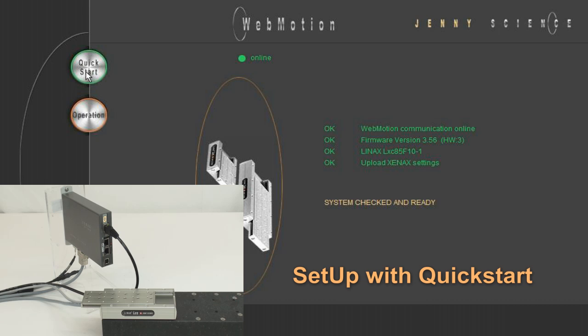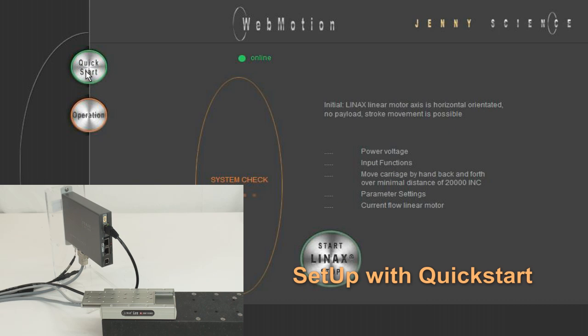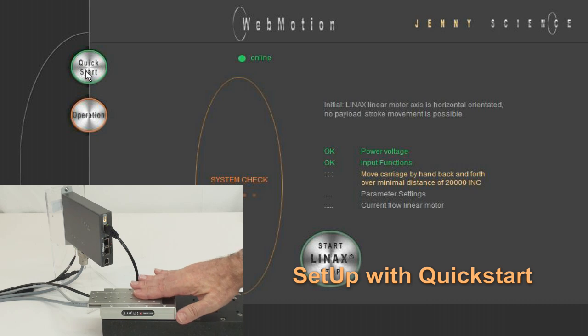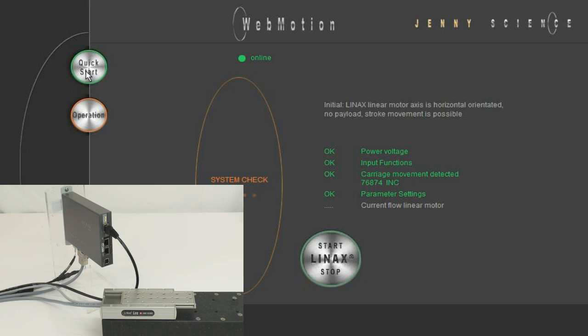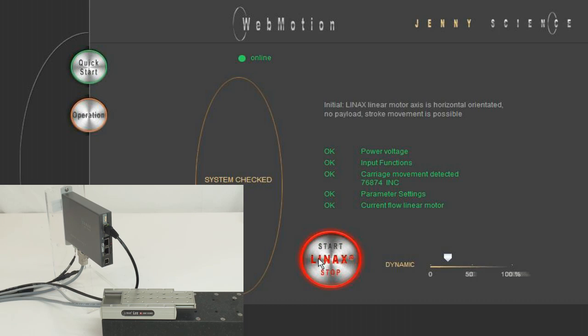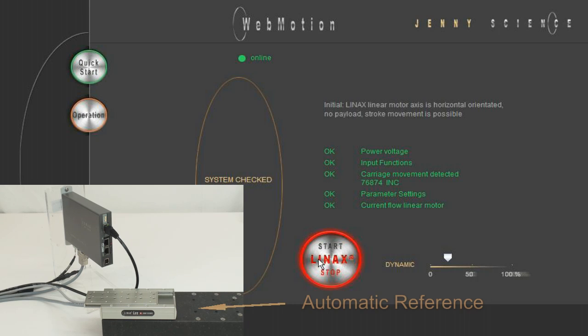An easy way to check if the axis is running properly is to push the Quick Start button. If power voltage and input functions are OK, move the carriage slider by hand over a desired distance. The parameters as well as the current flow through the linear motor are checked. As soon as the LINAX Start button lights green, we can start the axis.